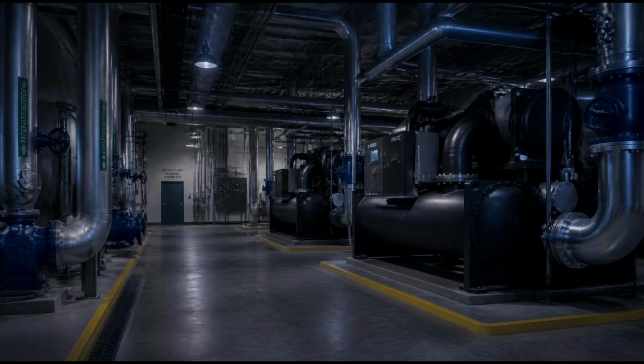mechanical systems. Most commercial HVAC systems rely on several distinct water loops, each serving a specific purpose and each maintained by its own set of pumps. There is the chilled water loop, which carries water cooled by the chiller to the cooling coils in air handlers and fan coil units throughout the building. The chilled water absorbs heat from the air passing across the coils, and then returns to the chiller, warmer than when it left, to be cooled again.